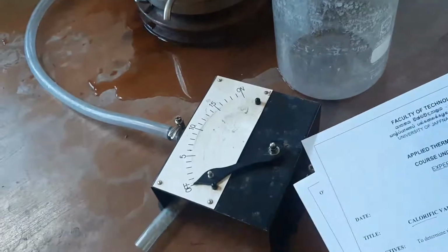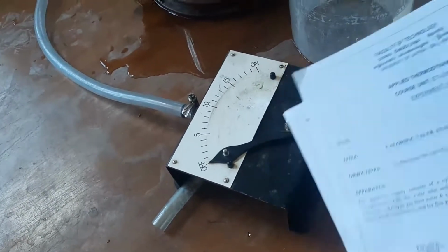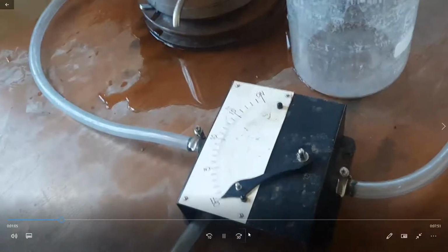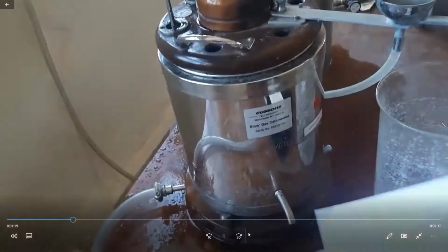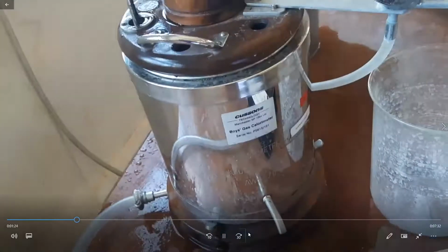If you want to, we can fully close it, or we can open it half or anything. By adjusting this, we can also change the flow rate of the gaseous fuel, the LP gas fuel. Then this LP gas will flow to this furnace. Inside this furnace, that LP gas will be burned. After burning that LP gas, that heat will be absorbed by the water.